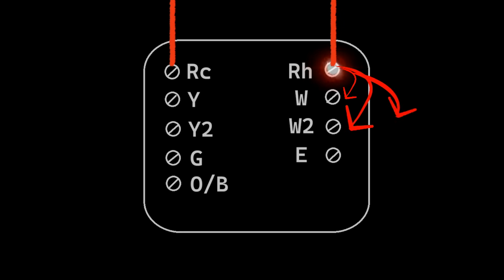Thermostats keep these two R terminals separate because we don't want to mix the circuits of two different transformers. So when you have a red wire coming from an air conditioning system landing on RC, it's only going to use that 24 volts to activate cooling related terminals like Y, Y2, G, or OB. When a separate wire is coming from your heating system and it lands on RH, that 24 volts is only going to activate heating terminals like W, W2, or E.